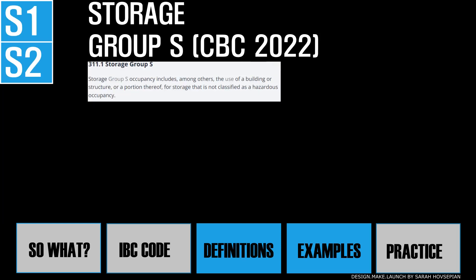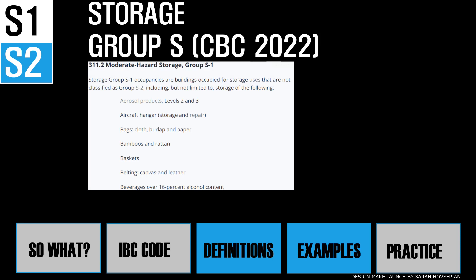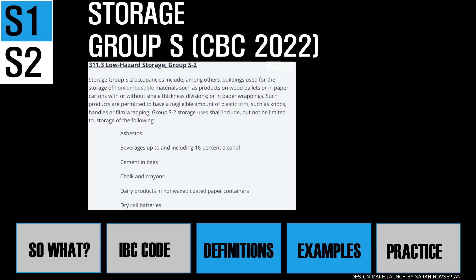The next category is storage group S occupancy — storage spaces not classified under hazardous occupancy. There are two subgroups, similar to F occupancy: S1 for moderate hazard and S2 for low hazard. Storage group S1 includes aerosol products, beverages, and a whole list of items. Storage group S2 includes non-combustible materials such as products on wood pallets or in paper cartons, asbestos, cement in bags, electrical motors, and food products. The distinction between S1 and S2 is whether the products are combustible or not.